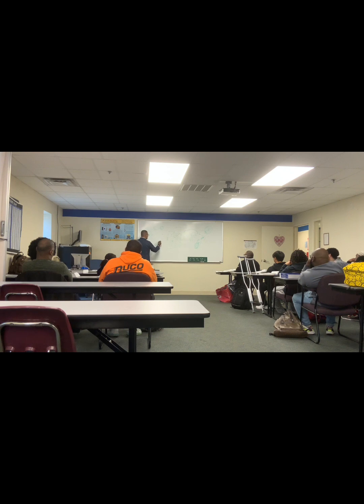And then you're going up straight, and you're going out the roof. So anytime we do this and do that, fittings, those are called fittings, cause restriction. Not always a real bad restriction, but it has to be accounted for, because it's restriction against direct flow where we want the air to be. So if we say we wanted 380 CFM out that vent, then we have to make sure all flow is coming that way. I'm not going to stay in this a long time because we have a whole class for this.